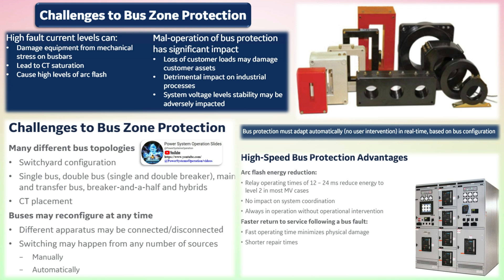Buses with statically assigned zone currents are well suited for the use of high impedance bus relaying if suitable CTs are available and do not require disconnect status inputs. For substations with terminals capable of switching between different buses, it is necessary to dynamically assign input currents to the bus zones of protection based on the disconnect auxiliary contact status.